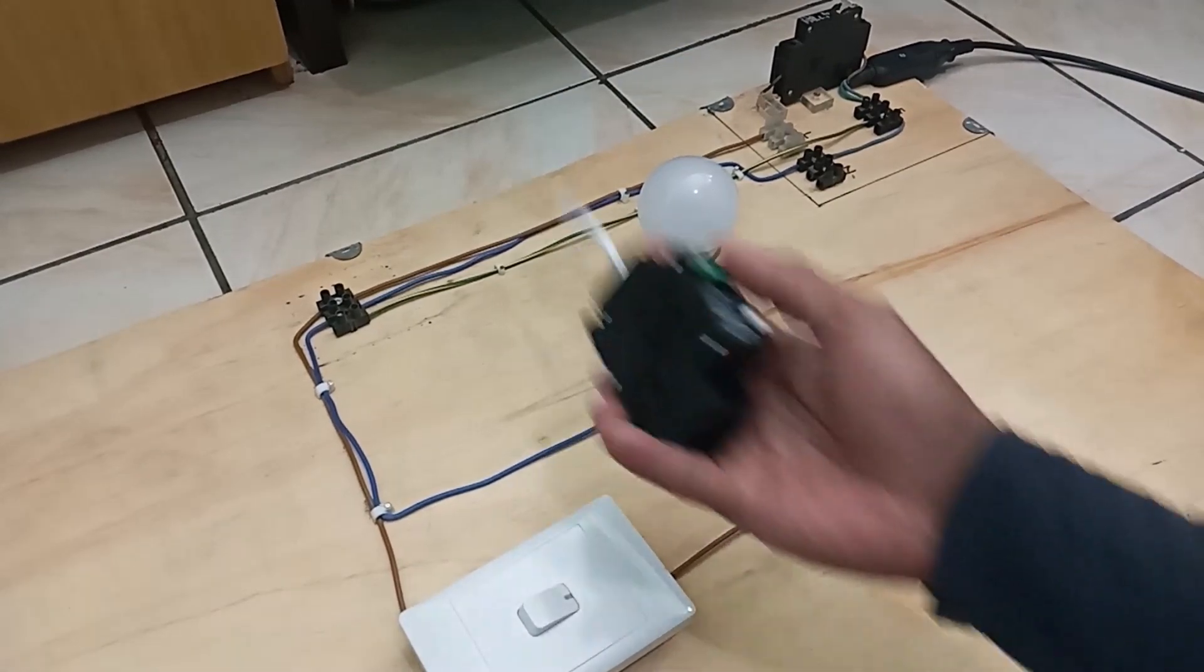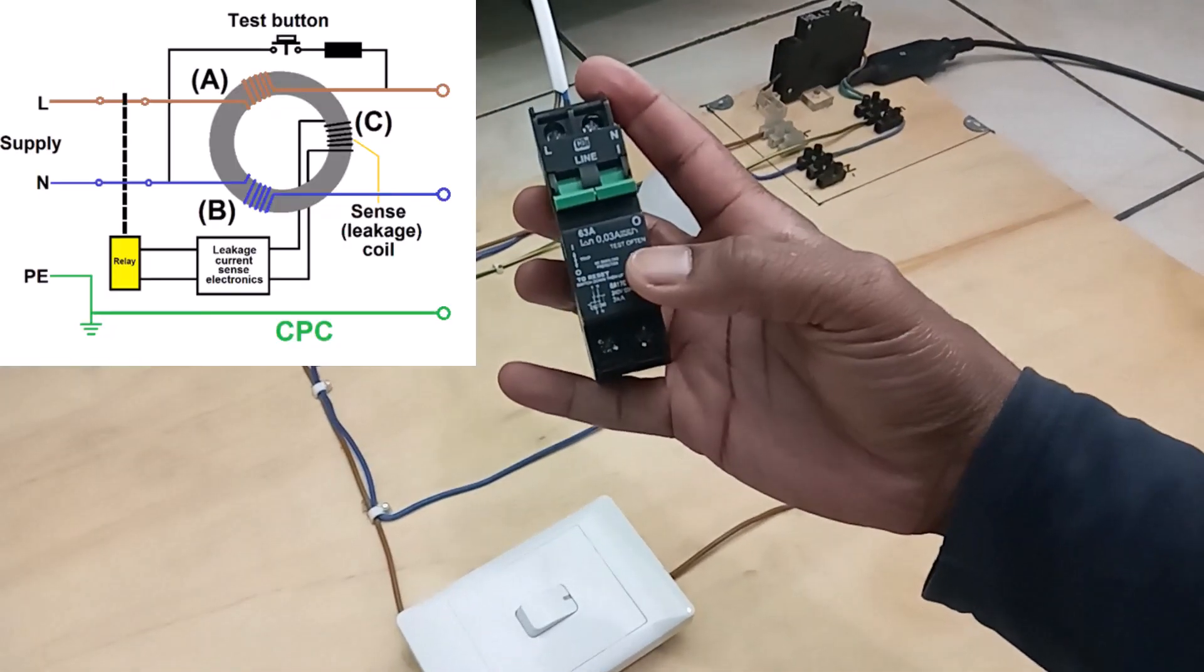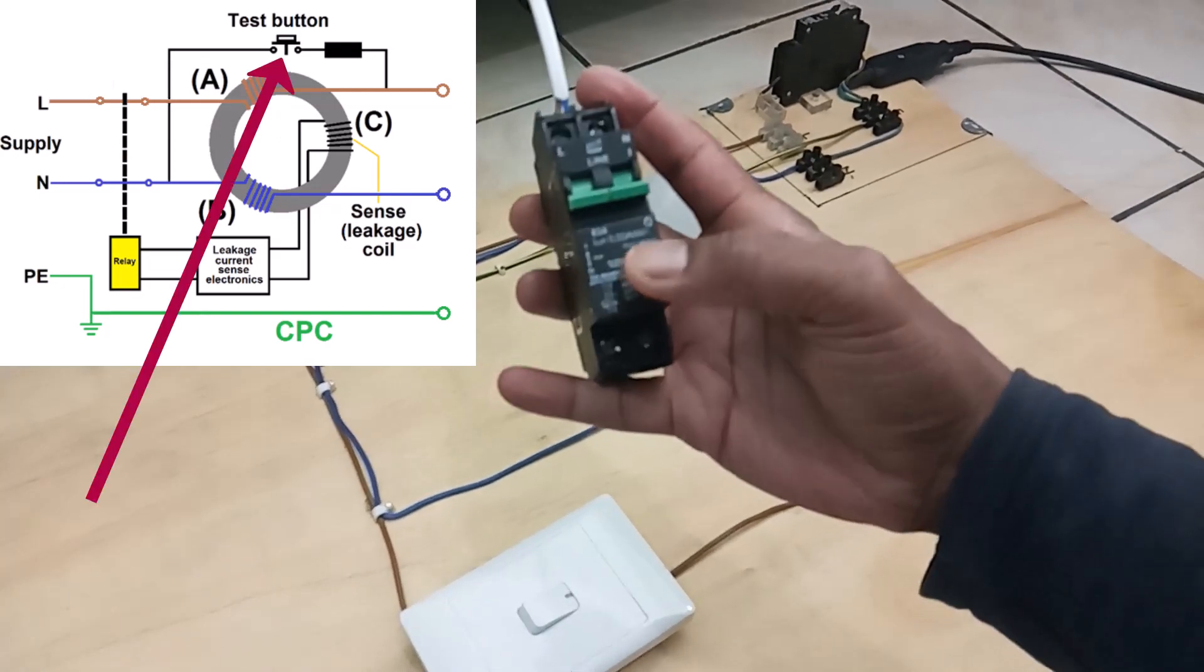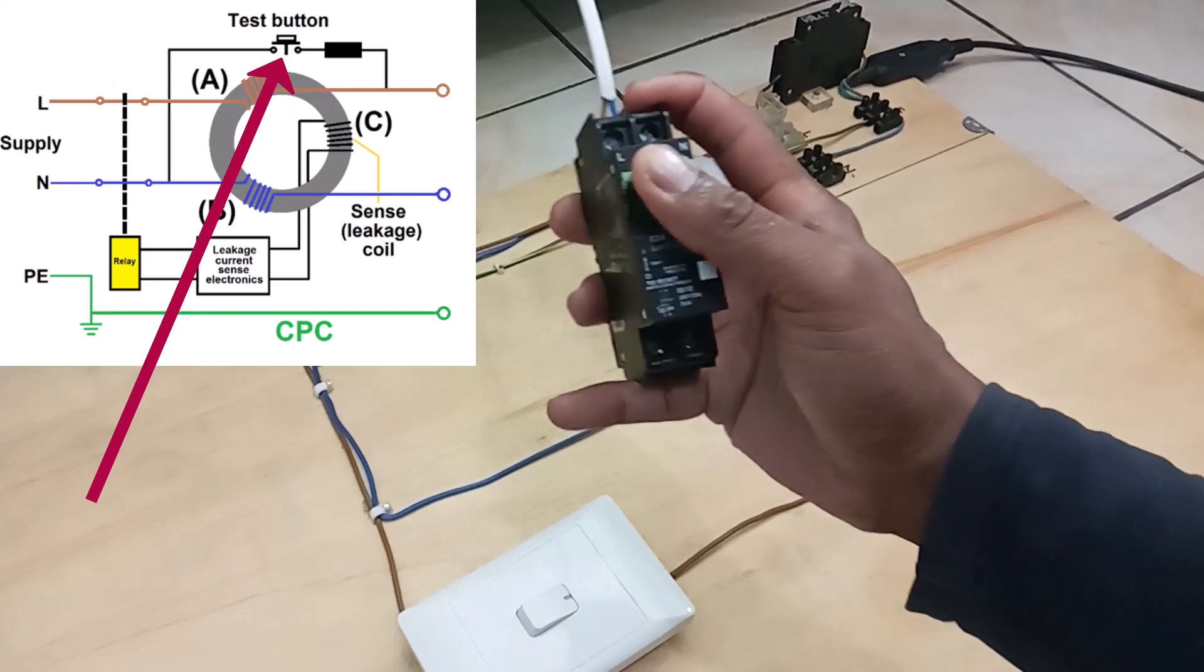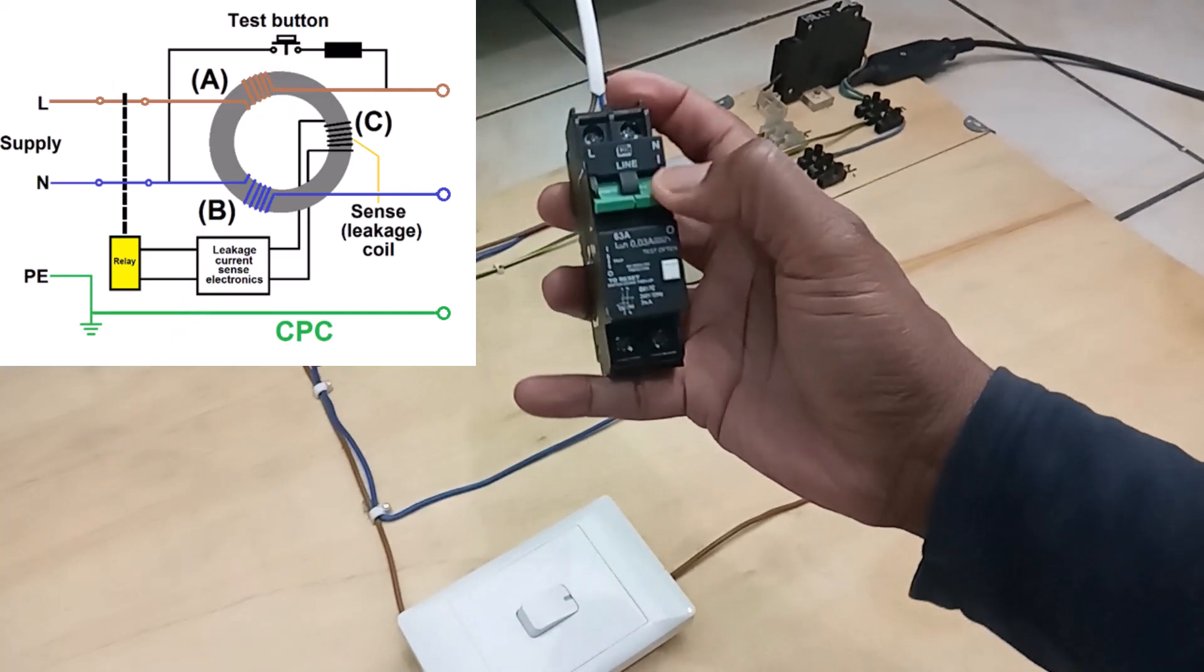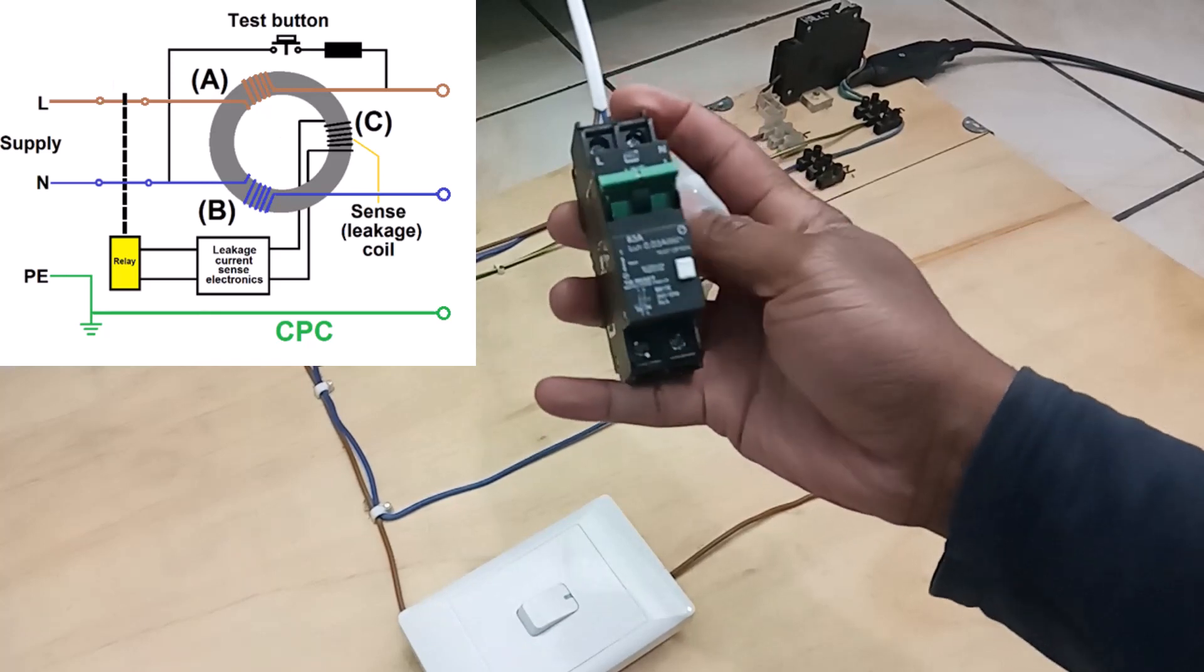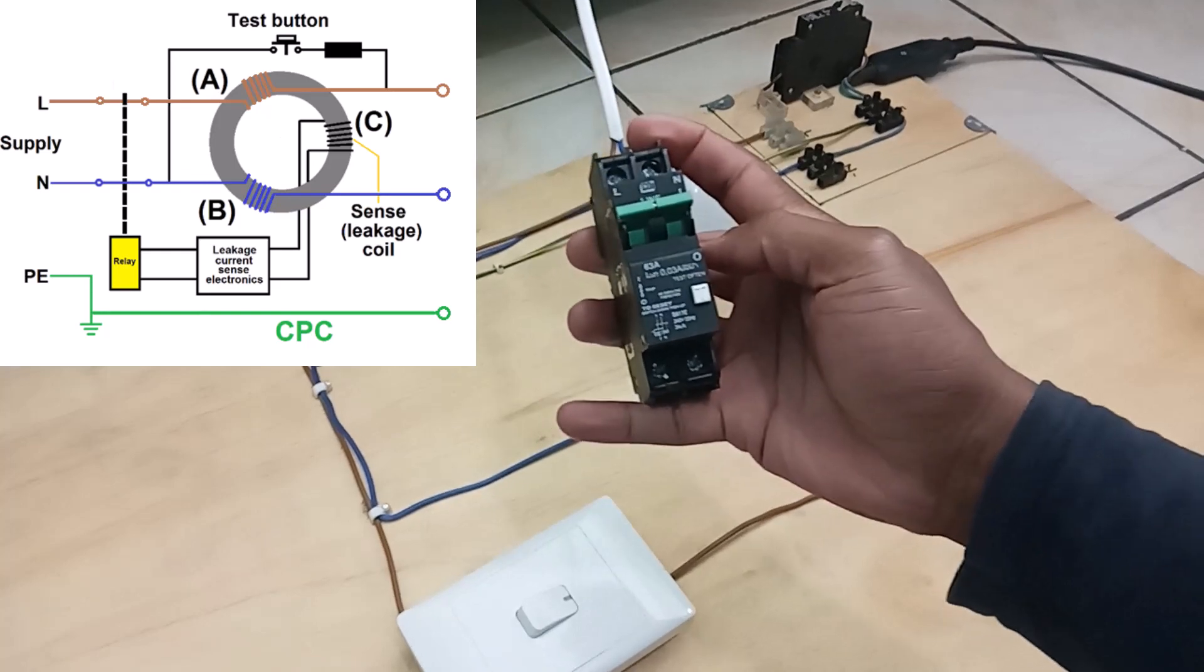Now, how do you test it if it's still working? You can see there is a white button here, this one. Now, as I'm pressing it, nothing is happening. Normally, if this thing is in the on position, if I press the white button, it should trip the circuit, and this will indicate that the internal circuit is still operating. It's functional.